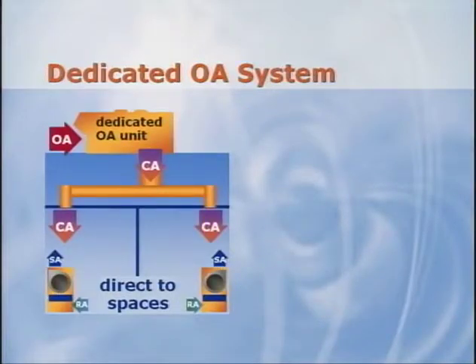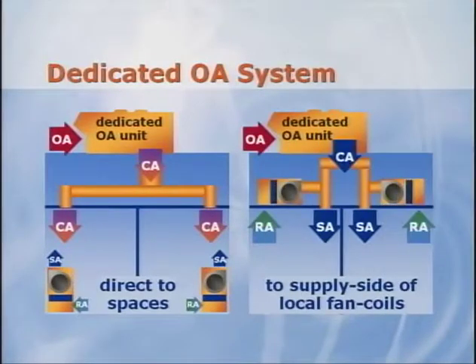The second approach is to duct the conditioned outdoor air directly to each zone, as shown in this slide. In this configuration, the fan coil cools or heats only the recirculated air to maintain space temperature. A variation of this second approach is to duct the outdoor air to the supply side of each fan coil, where it mixes with supply air before being delivered to the zone. Again, the fan in each local unit only needs to move the recirculated air, rather than the mixture of outdoor and recirculated air. When the conditioned outdoor air is delivered directly to the zone at a cold temperature, rather than reheated to neutral, this cold air offsets some of the space-sensible cooling load, allowing the local fan coils to be smaller and use less energy.